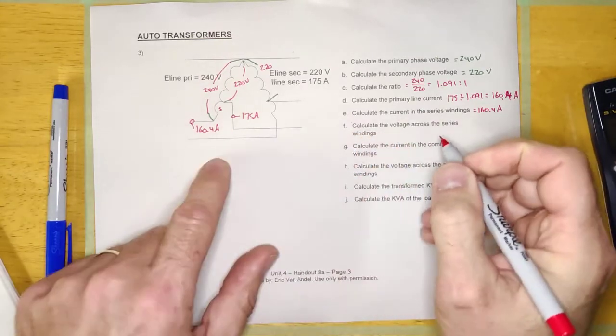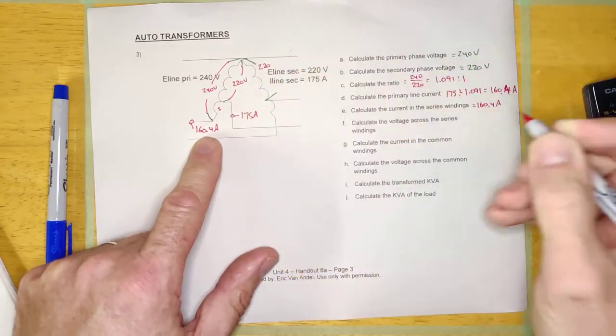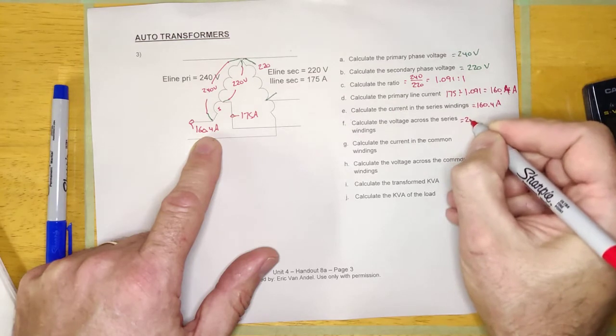Calculate the voltage across the series winding. There's the series winding. Kirchhoff's law - I've got 240 volts from here to here and 220 volts from here to here. How much is there? It's 20 volts. This is going to be 240 minus 220, 20 volts.